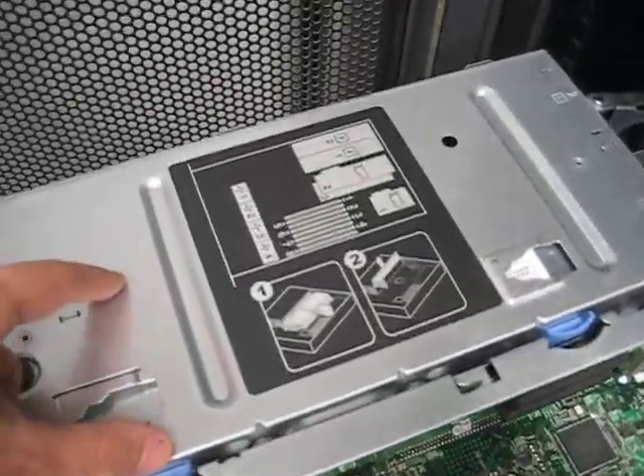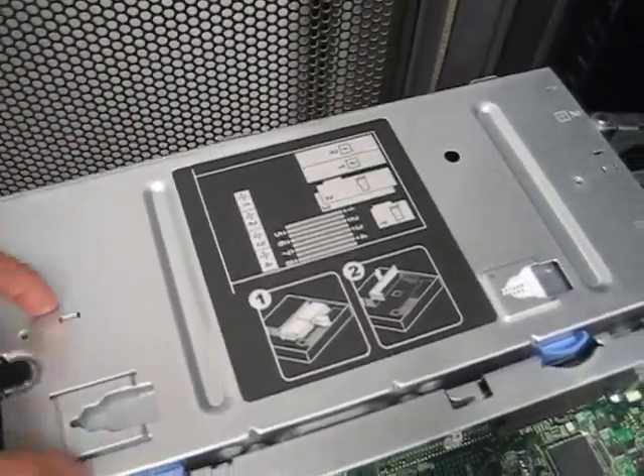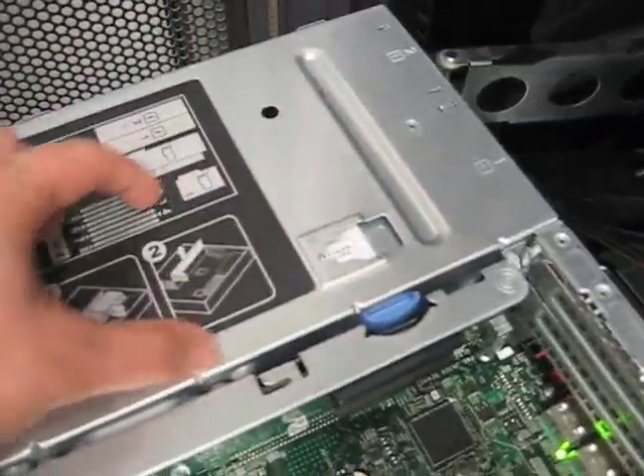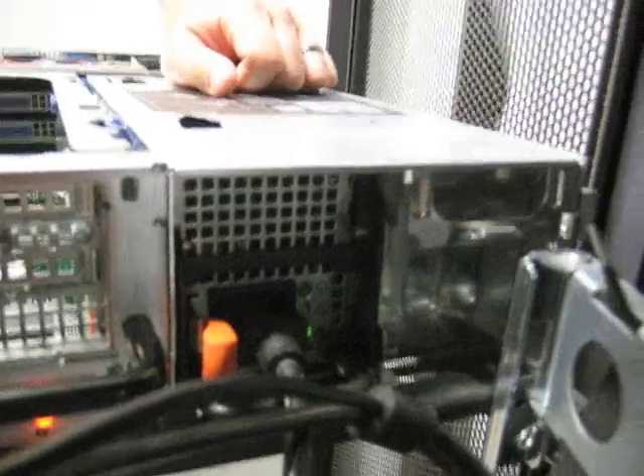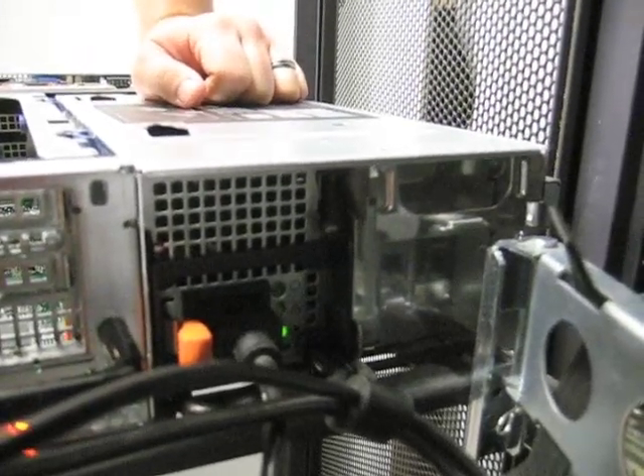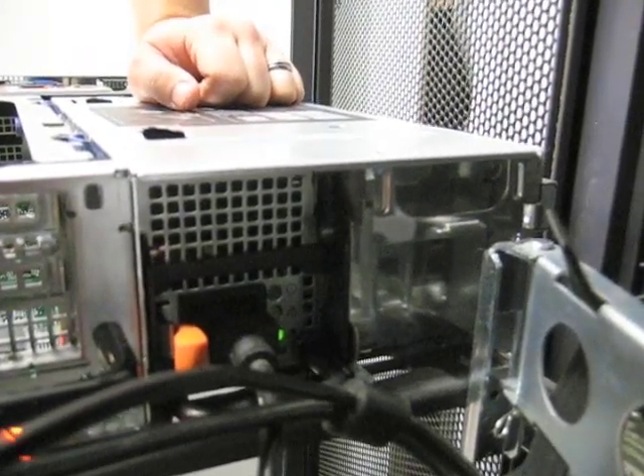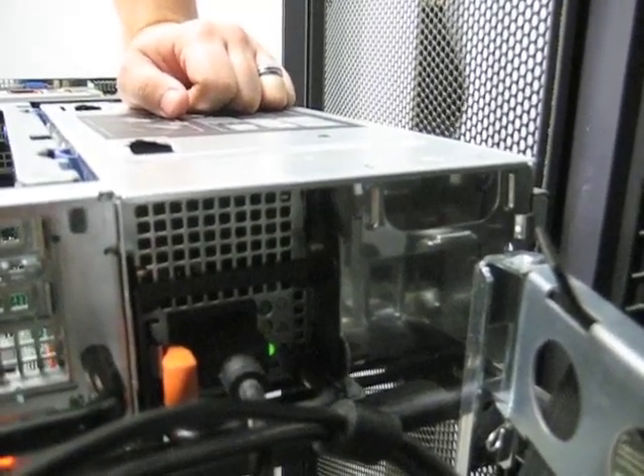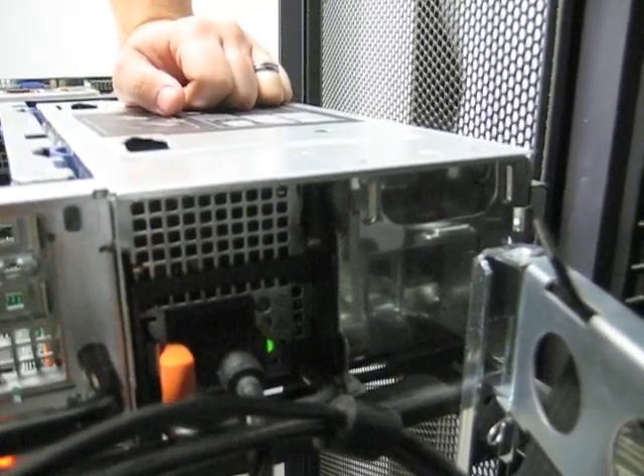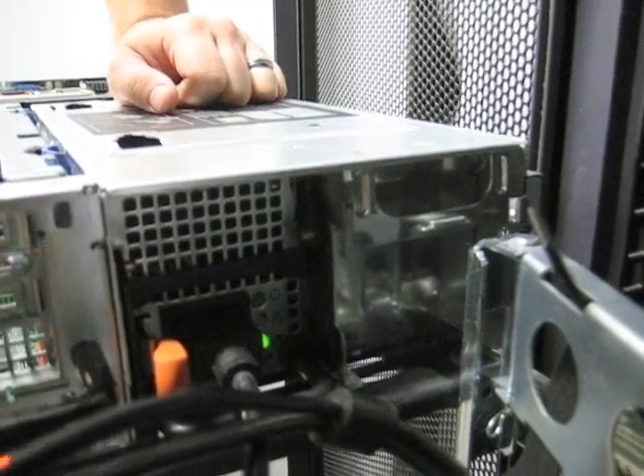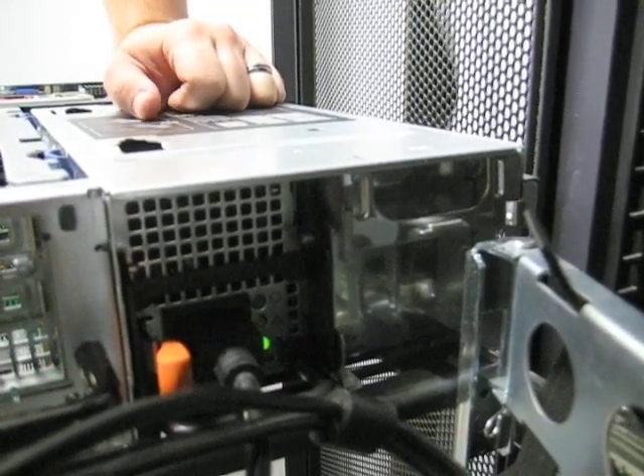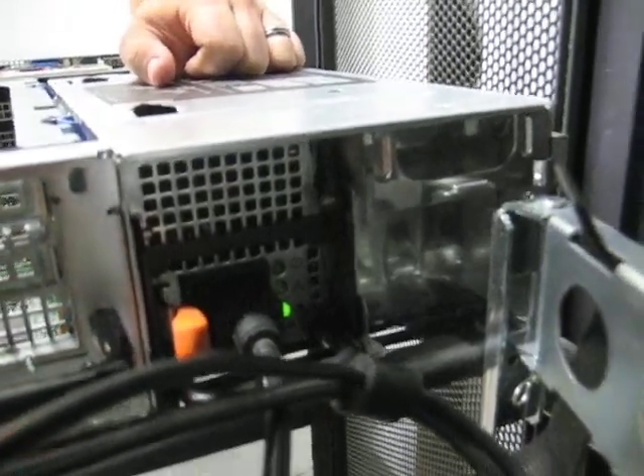Also, there's room here for two power supplies. It's hard to see, but the power supply can actually slide out the back here. I don't know if you can see that. There's also an empty slot for an additional one. That's so that you could have two power supplies in case one fails. You could also connect one power supply to one circuit, electrical circuit that is, and one power supply to the other electrical circuit, so that if one breaker trips or maybe you have a generator backup on one, you would not lose power by unplugging one or the other.